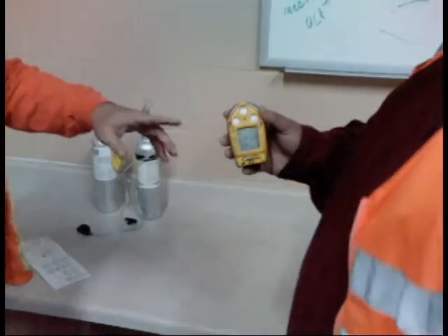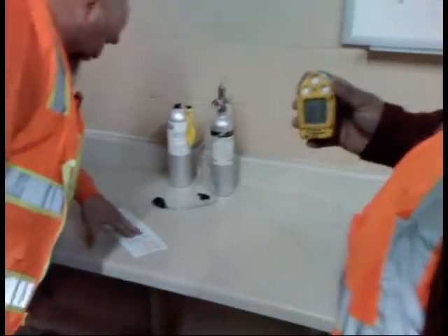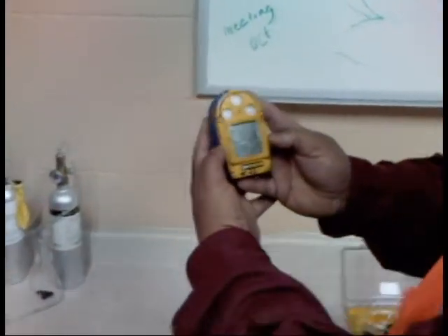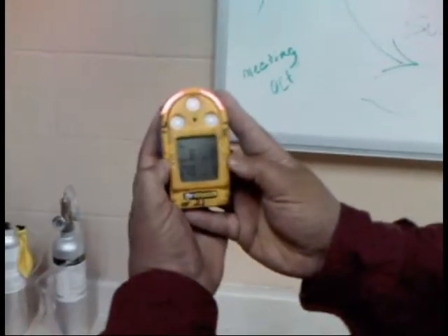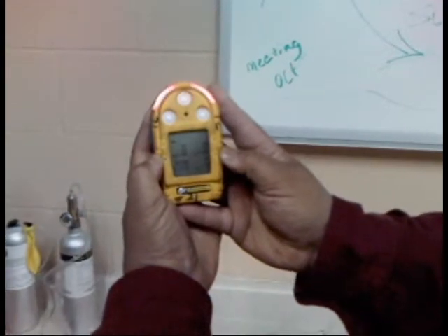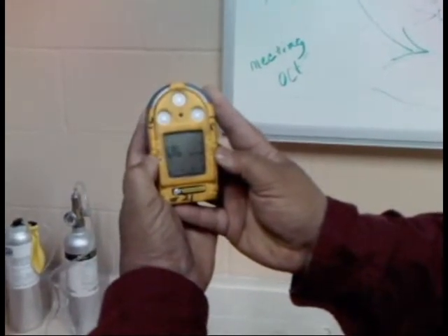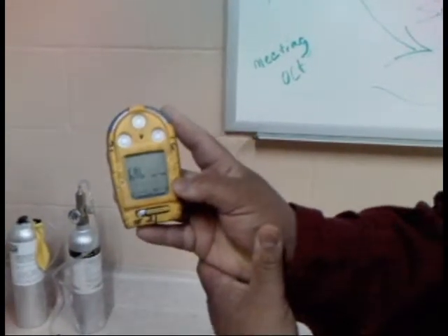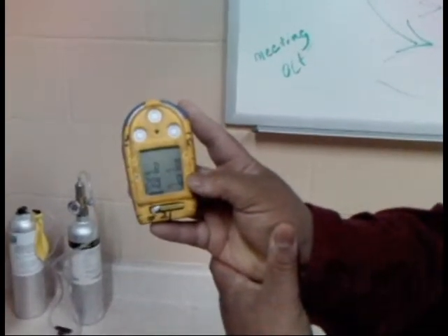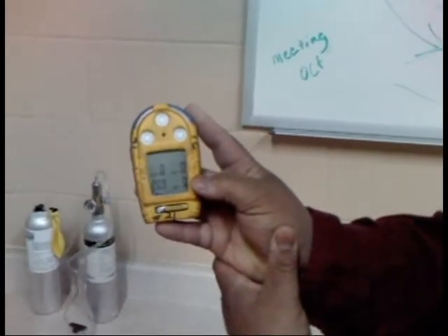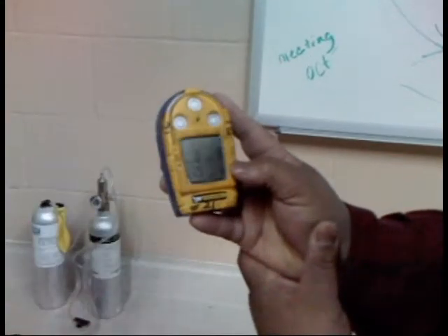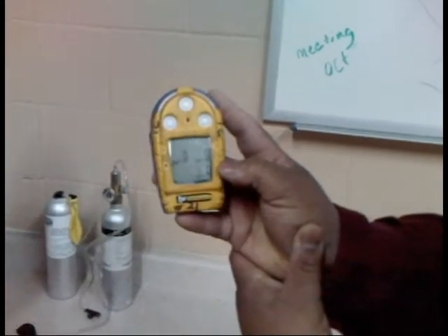Okay, now we're set. Now the first step in the calibration is to press the circle and the down arrow simultaneously and hold for about 5 seconds. Detector beeps 4 times, as you see, and then the display will flash, what's that say? Auto zero. Auto zero.